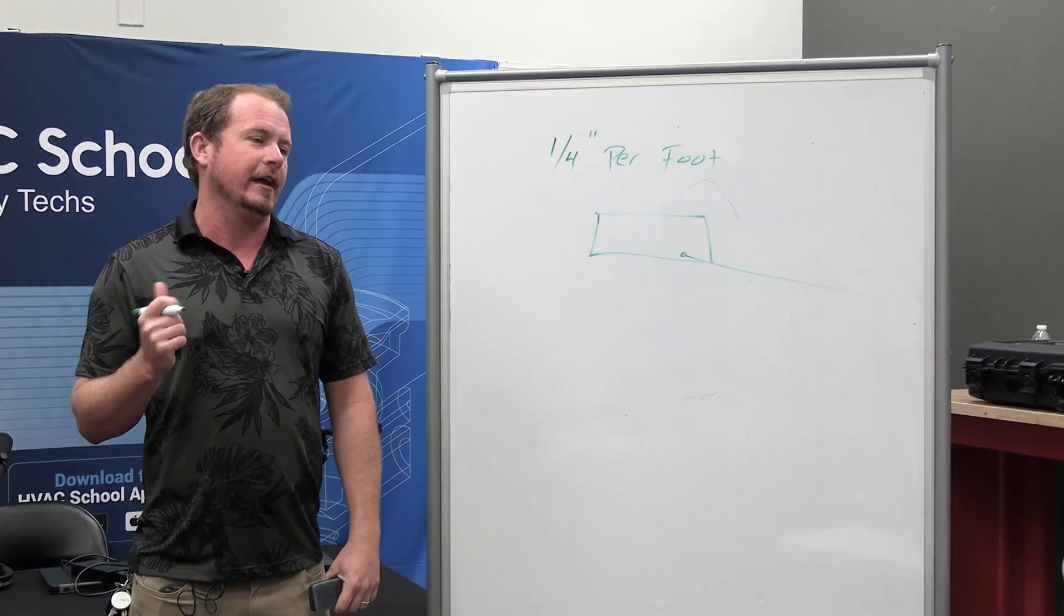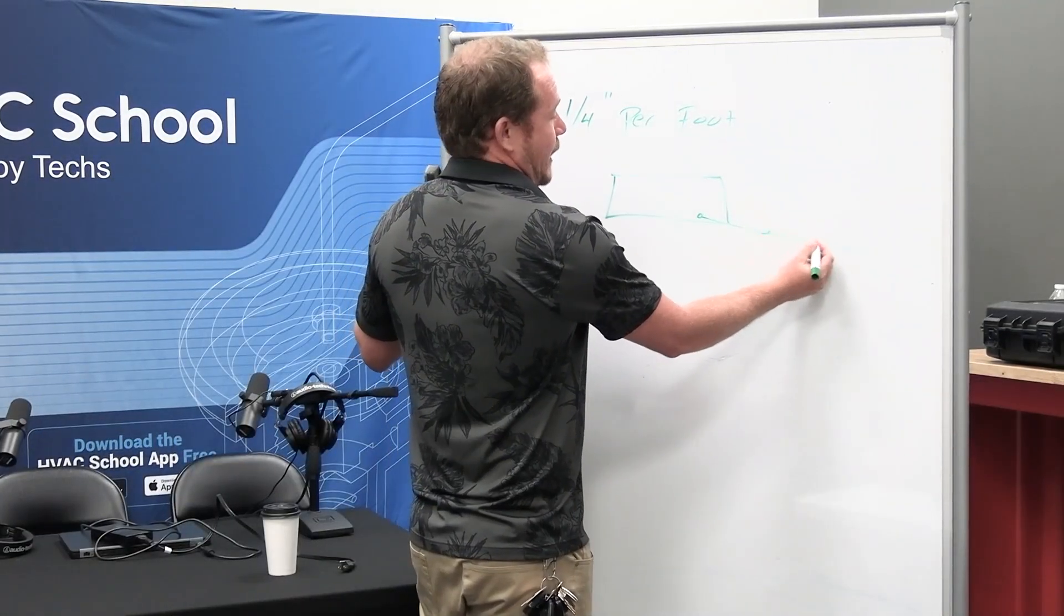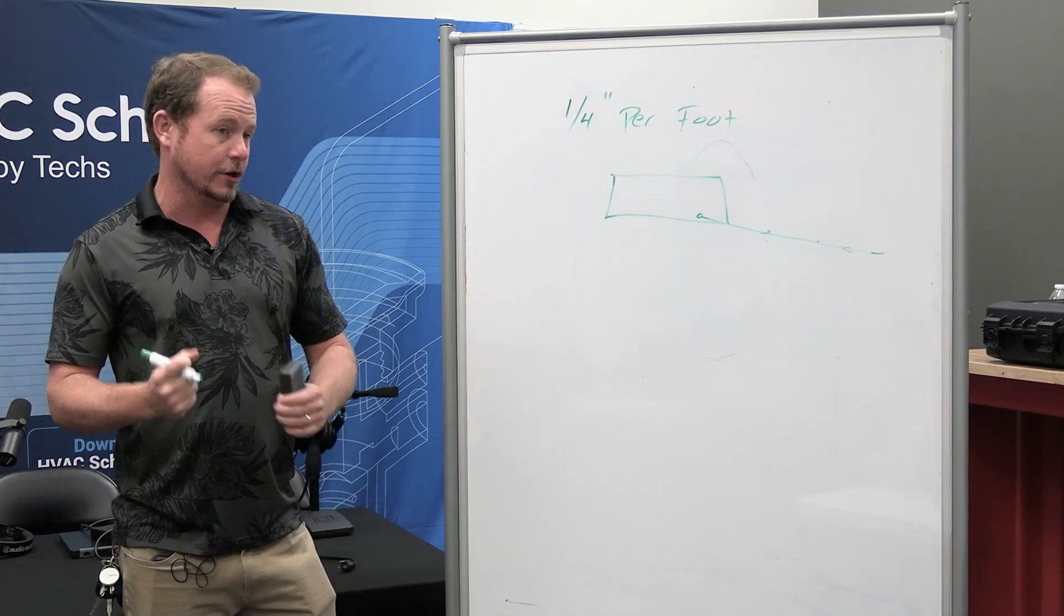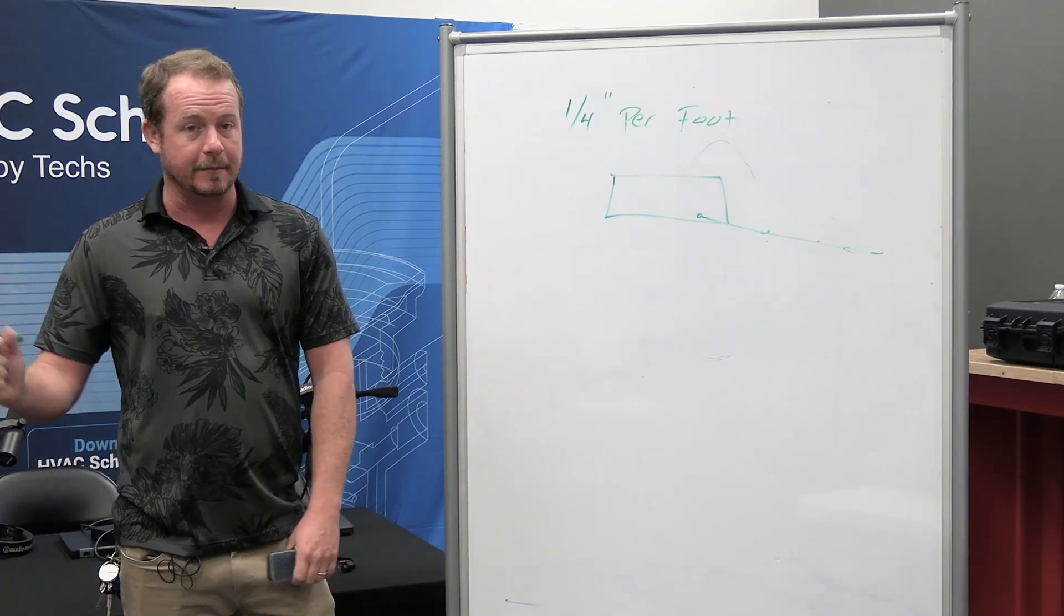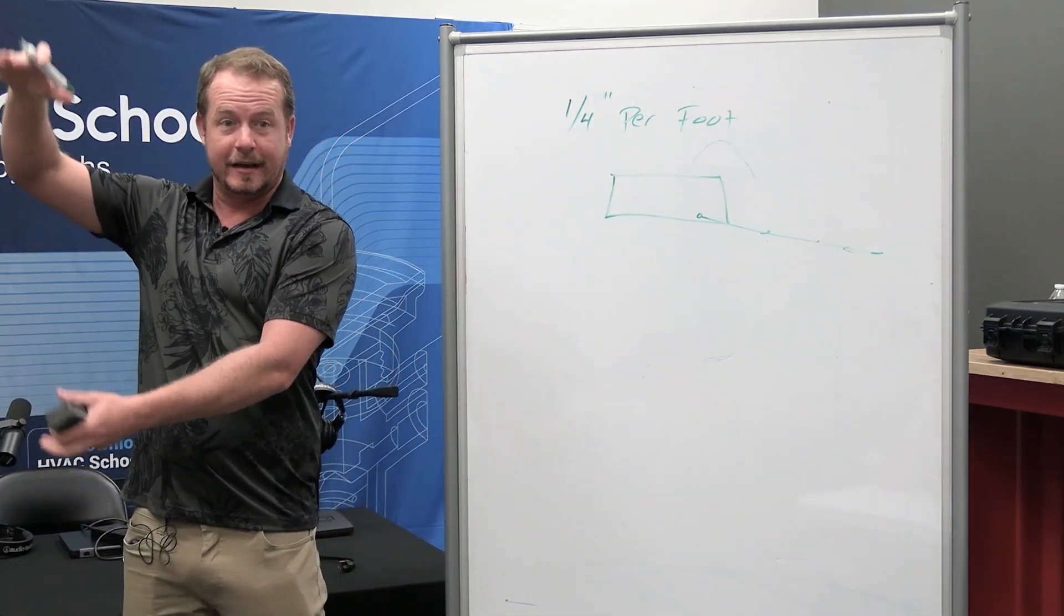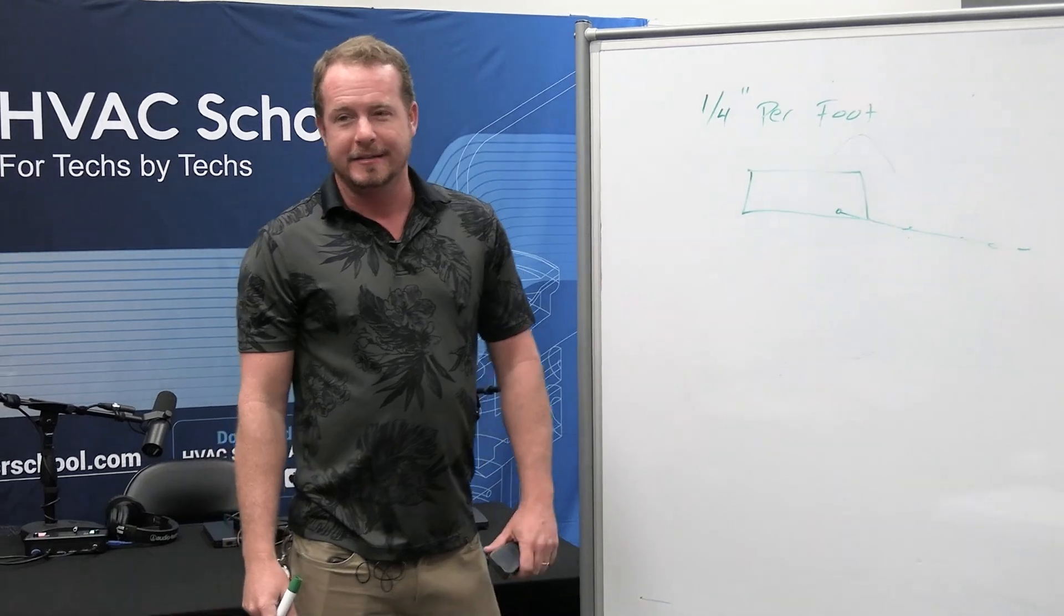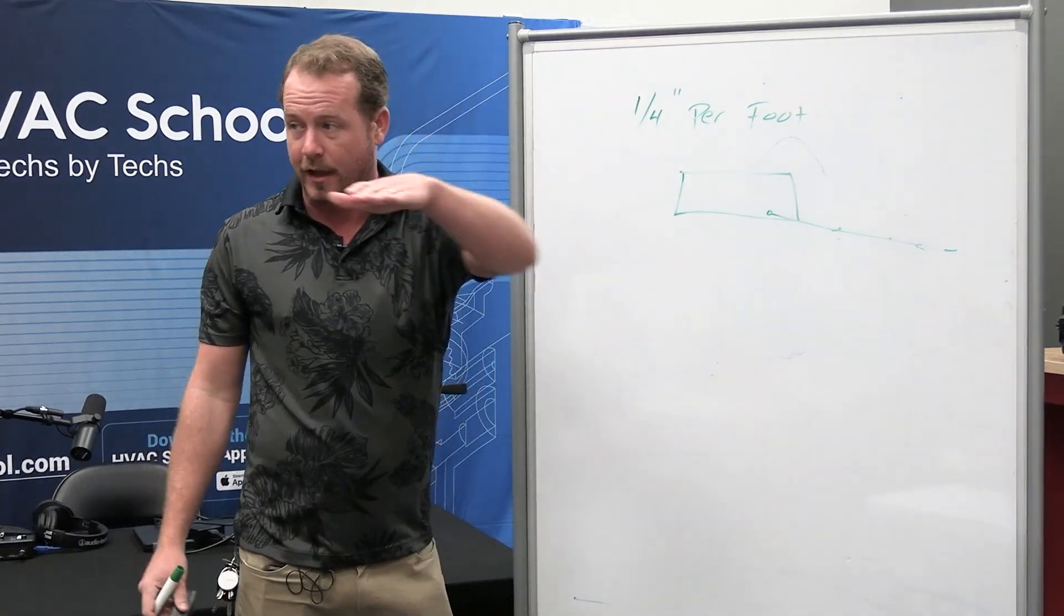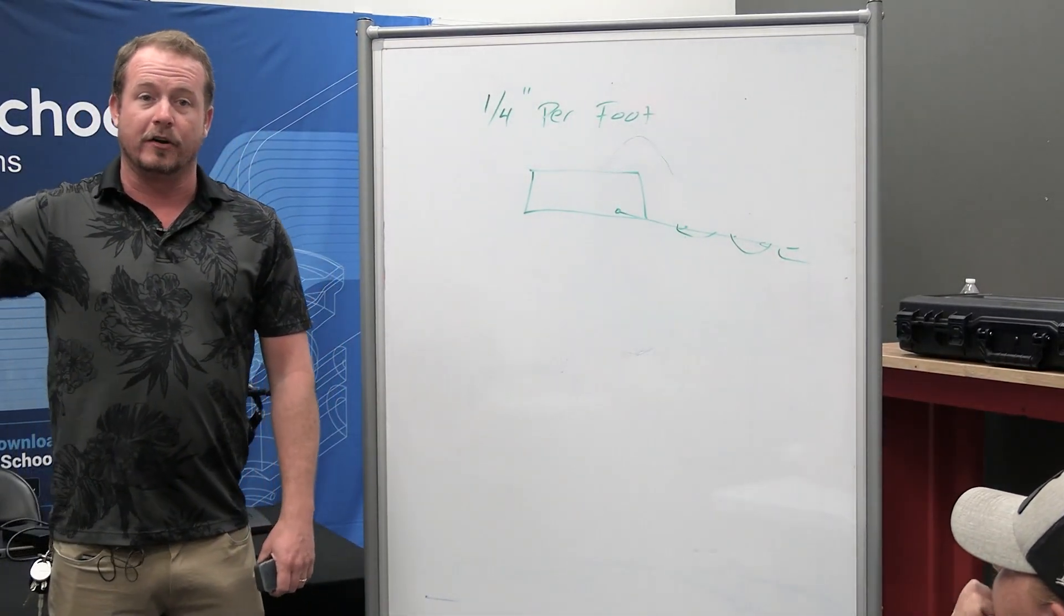So if it's a horizontal unit, right up in an attic and we've got a drain and this drain is going this great distance, we have to make sure that we get that quarter inch per foot run out. I know I'm just the quarter inch per foot is what I always quote. Just so that way we're safe. We have to make sure that it's strapped properly. So that way we don't get sag kind of a good standard is at least every four feet, minimum, every four feet, good, solid bracing of some sort that gives you your proper pitching. This is also true if you're on roofs, you're draining a roof drain, something like that, same sort of thing. You have to make sure that it's actually got on stands. And if you're running a really long distance, that means near the unit, you need to get it higher up so that way you can get more fall before it gets all the way over. Right. Over time, what tends to happen if you go to a system that's been running a long time and now it's having drain issues, a lot of times it's because over time you lost a brace or it was never braced properly in the first place. And they were just relying on the PVC. And what does the PVC do? Starts to sag over time.